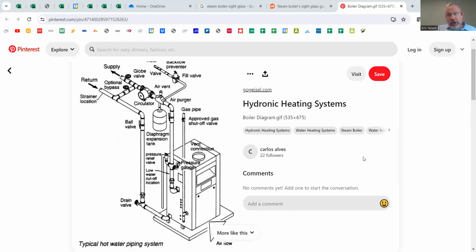In the olden days, and there could still be some very old ones out there that are gravity, meaning they just use the convection of the hot water: it rises up, then it cools and comes back down. Very inefficient, very poor way to do it. They may still be out there in their antiquated form, but almost all hot water boilers use a circulating pump. So when you see a pump on there, it's almost never going to be a steam boiler. So that's one indication.